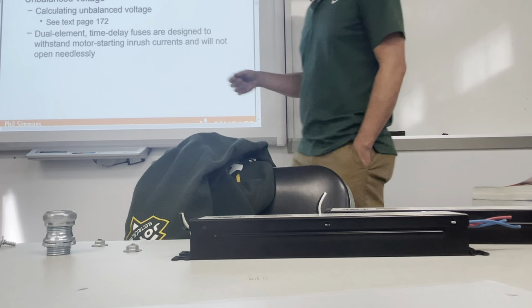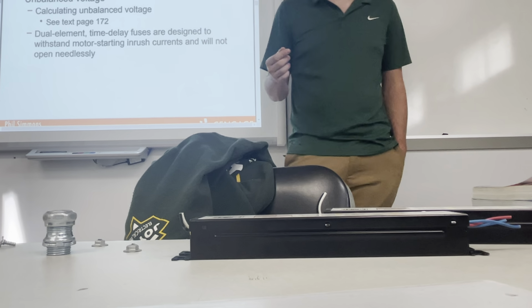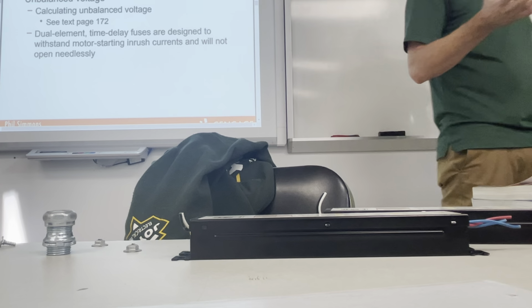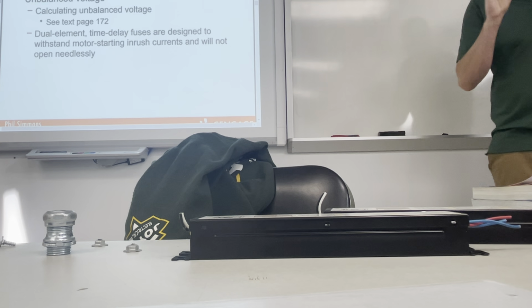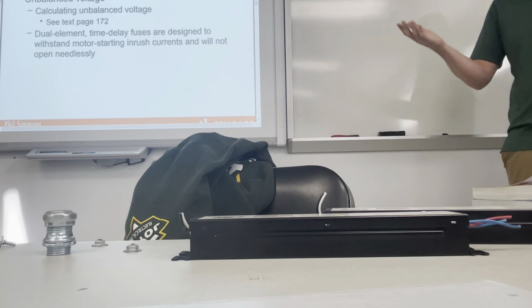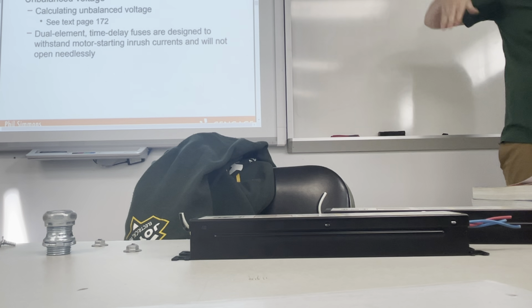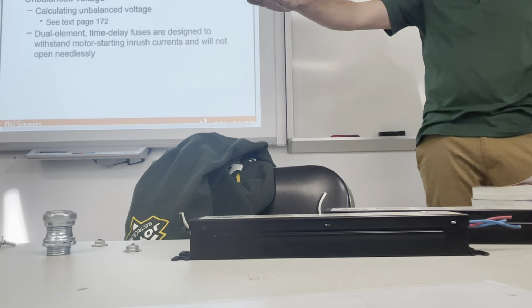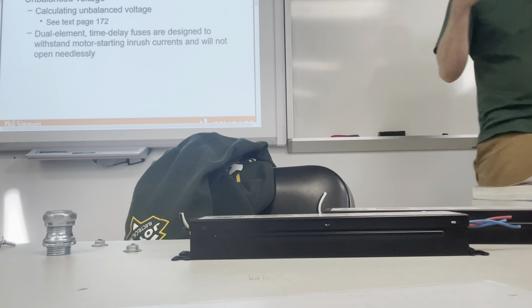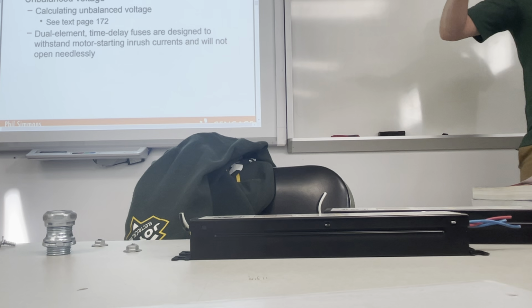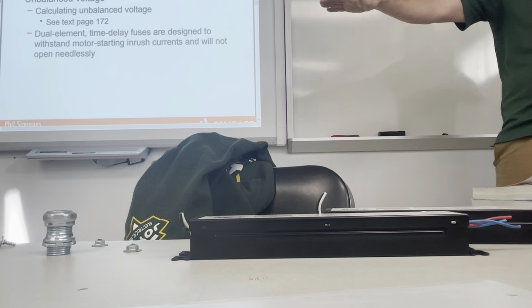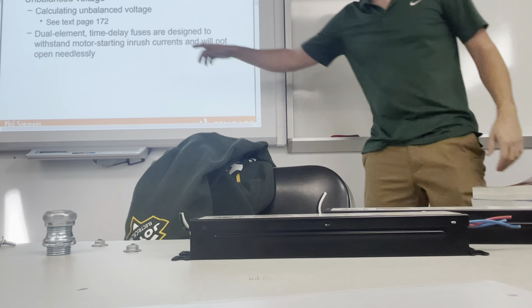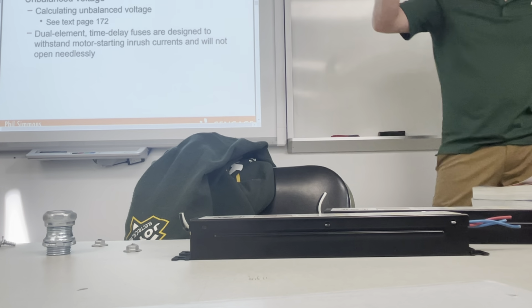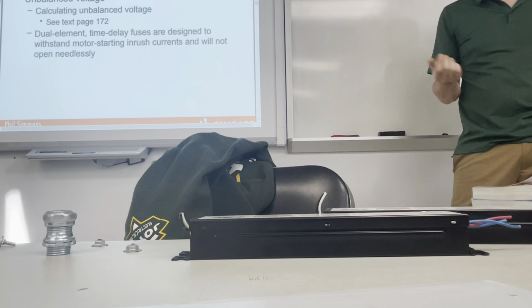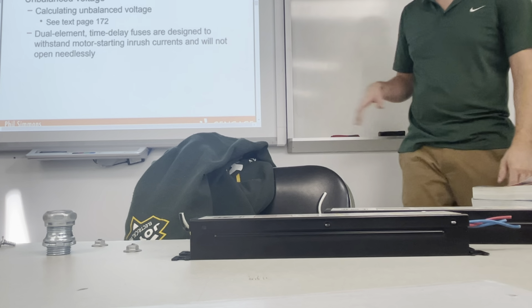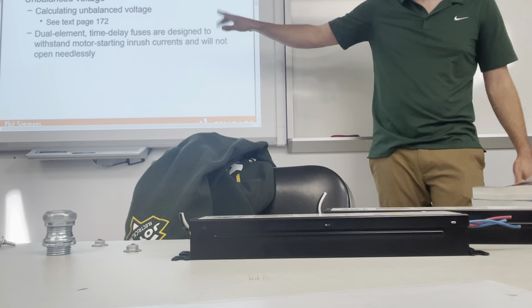That's what all of these dual elements, the time delays, your overload relays, they all have an inverse kind of effect. If you push just slightly more, it'll let that go for a couple seconds because motors have that initial startup current. So it's going to come up high, and then it's going to stabilize. It gives that overload time to heat up and cool down while that motor is still running, because it has to allow that little bit of variance. Same thing with these time delay fuses. They allow a little bit to go by, but if you were to put a lot of amperage through it, they would pop pretty much immediately. So, any questions with dual element fuses or time delay fuses or overloads or anything?